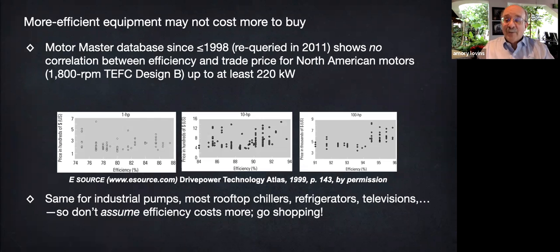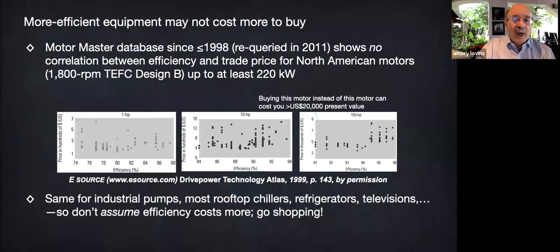And they were surprised to find there was still no correlation between efficiency and price for common motor types up to at least 300 horsepower, 220 kilowatts. So as shown in the right-hand graph, around 1998, you could buy the most efficient 100 horsepower induction motor cheaper than nearly the least efficient one with otherwise comparable specs, and thus you could save a present value above $20,000 per motor.